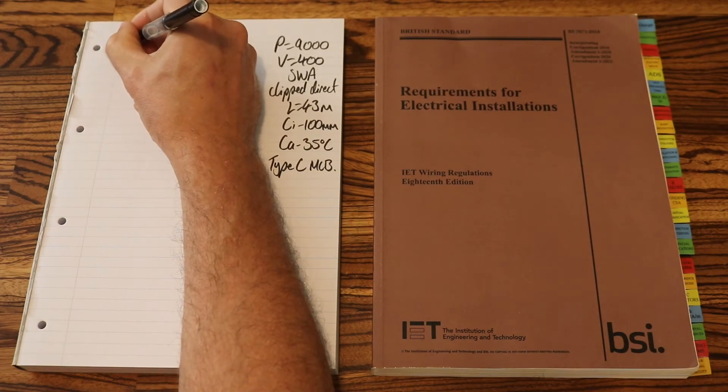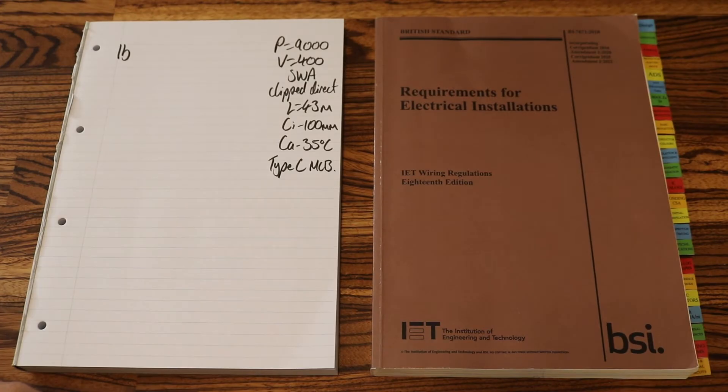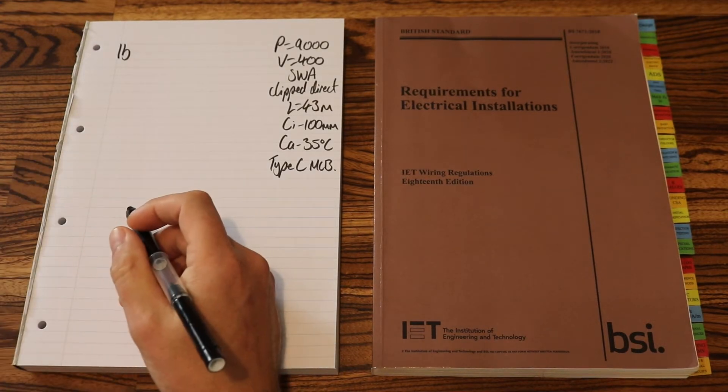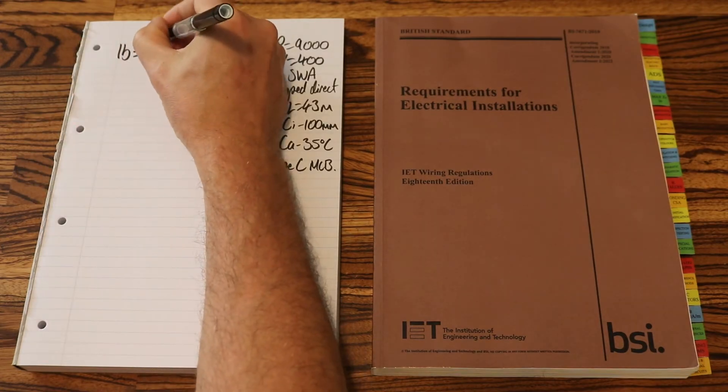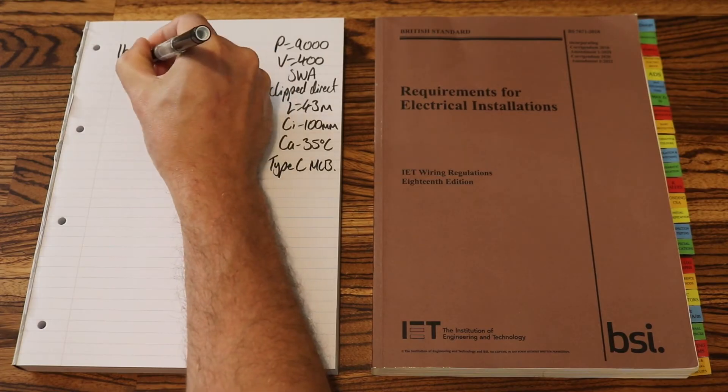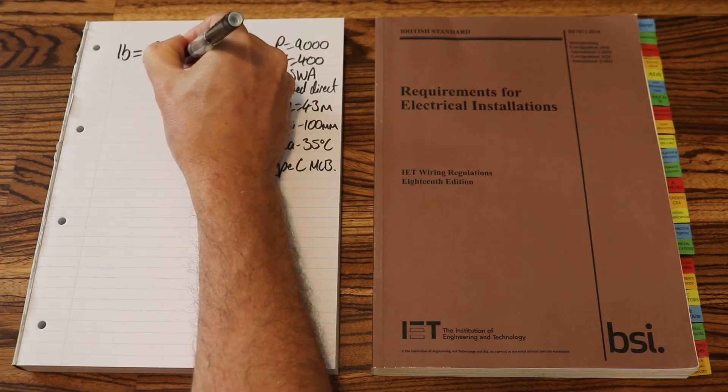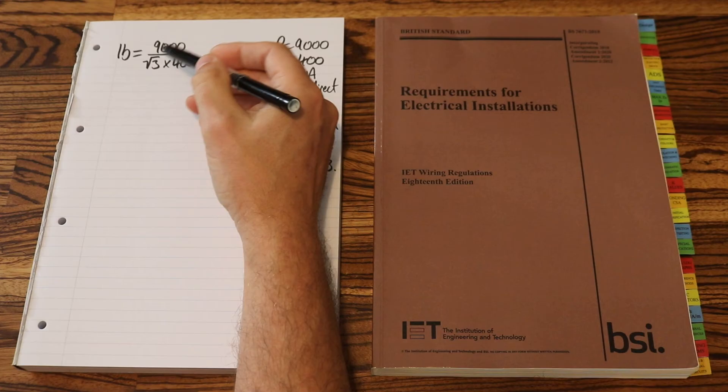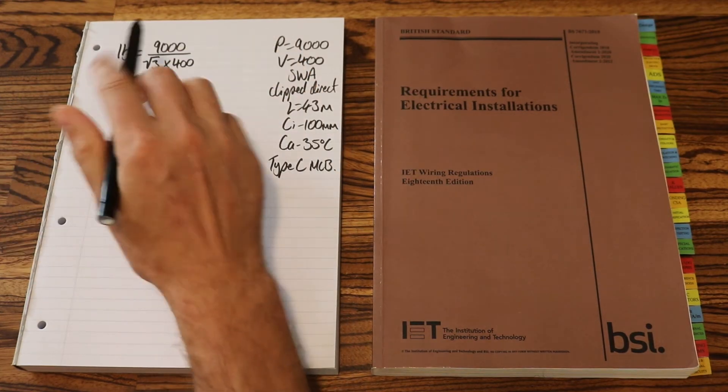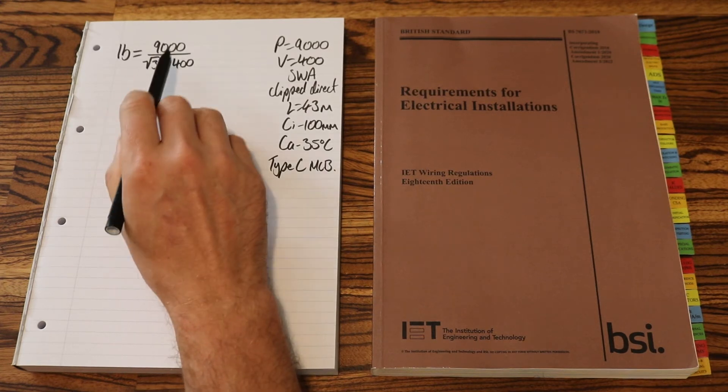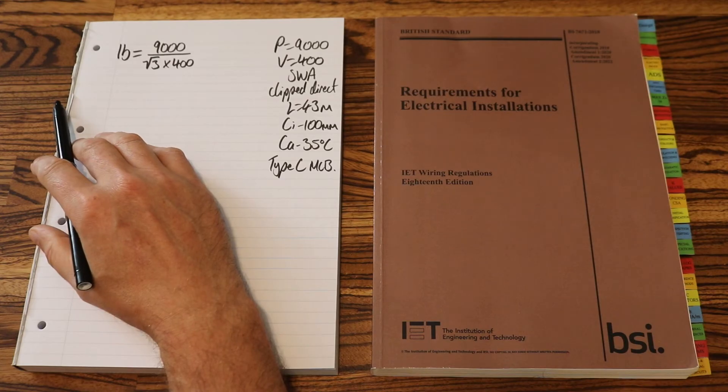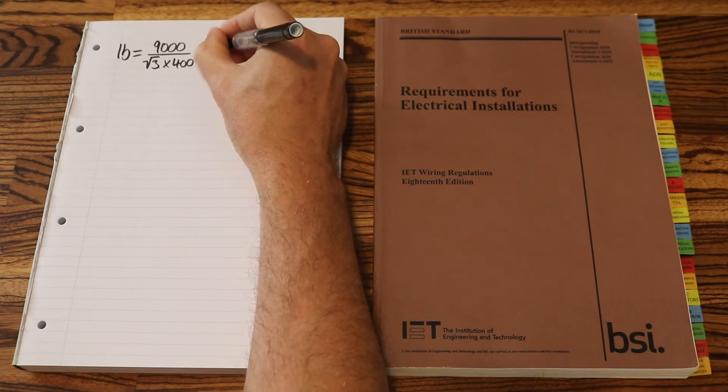So let's get on with our cable calculations. Our first step, IB. Now if you've gone onto the website and you've downloaded the cable calculation guide, we are going to be doing steps 1 to 8. Step 1 tells you all of the different ways of working out that IB. So when we've got a three-phase circuit, our IB will be 9000 over square root of 3 times 400. When you punch this into the calculator, be wary that you don't end up square rooting the whole of the bottom part. And with some rounding, that comes in at 12.99, so we'll round that to 13 amps.